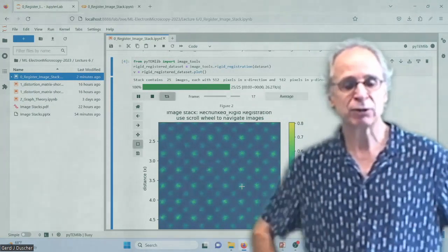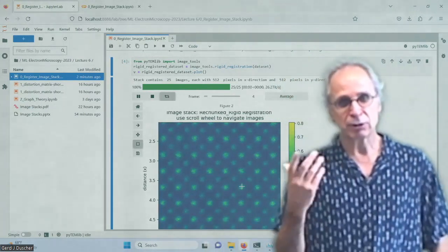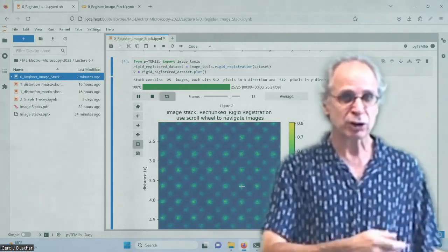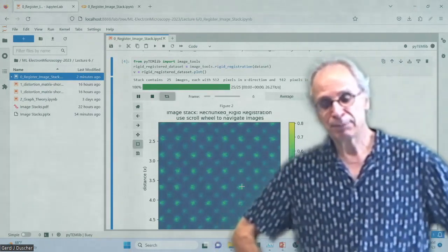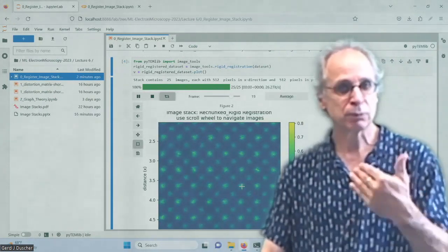And so you will introduce currents back into the magnetic material, so your pole pieces, and that will disturb this. So this so-called eddy current is one option. Then, of course, you have slight charges on the sample, slight charges within the microscope, and all of that would be random, while the distortions in X and Y and in the scan, possibly the amplifier, would be reproducible.